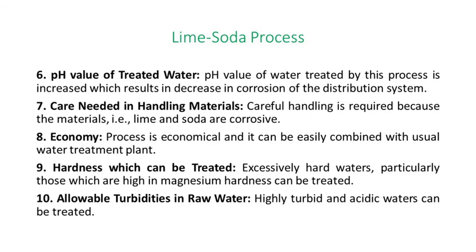Next, economy. If you consider the economical process, the lime soda process is economical and easily combined with other water treatment methods. But the zeolite process is a costly process. Okay, so the hardness which can be treated: in the lime soda process, excessively hard water can be treated, and in the zeolite process, raw water with hardness greater than 800 mg per liter cannot be easily treated and cannot be treated economically.